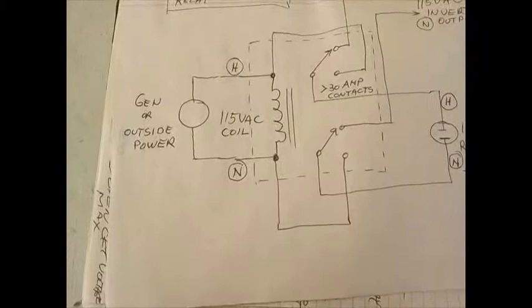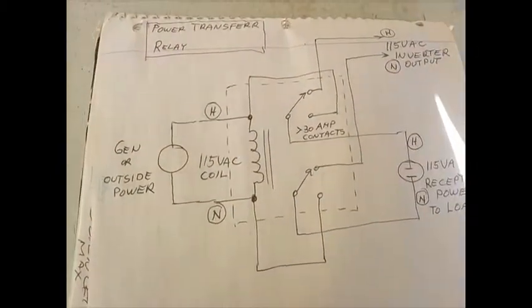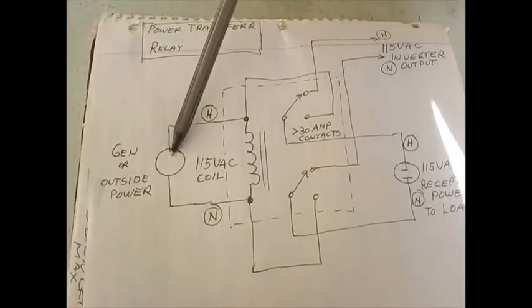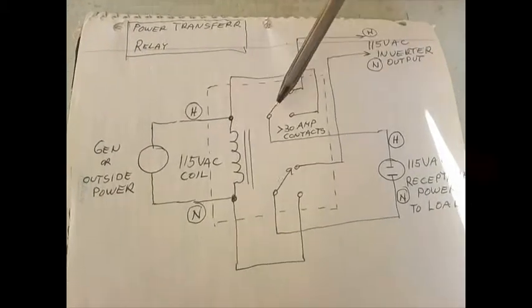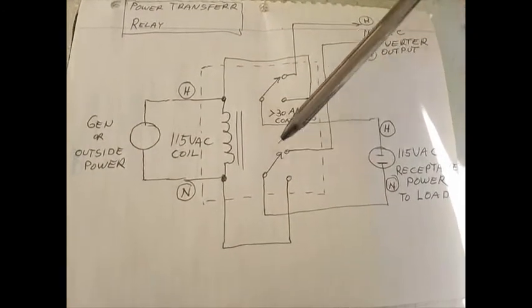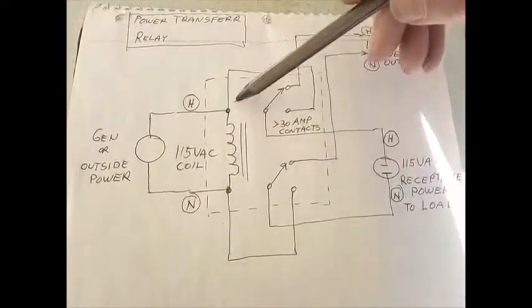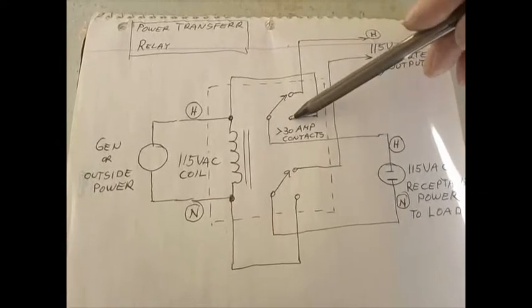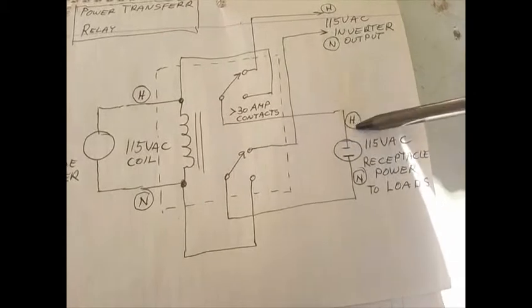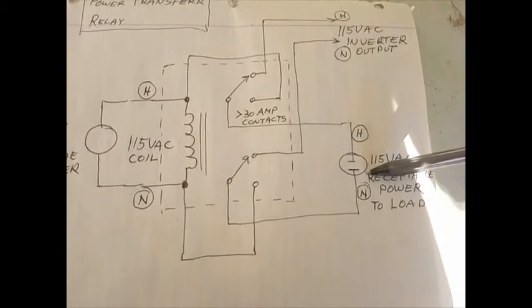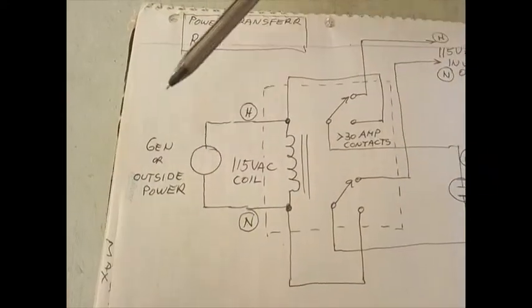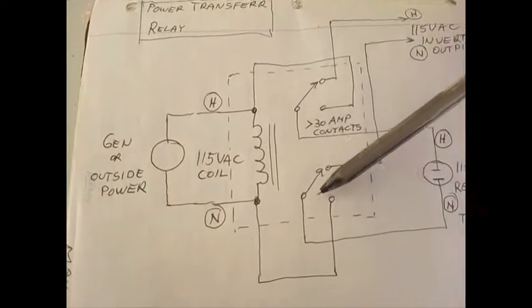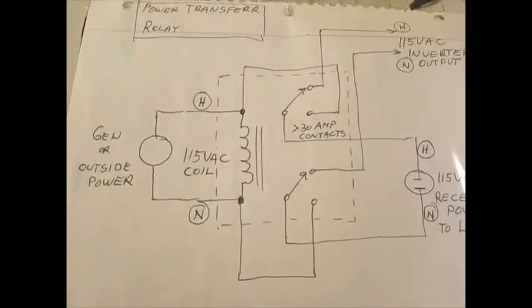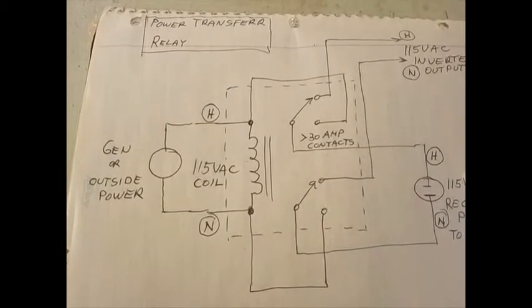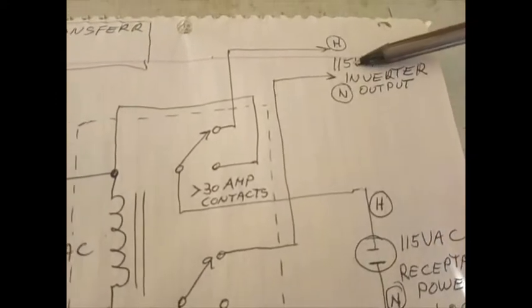I just want to show you a drawing of what's inside that box. Here we have the outside power or the generator, and when that is powered up, it'll energize the coil and make these switches go into the lower position. And then you have the straight through outside power coming to those contacts when the armature is pulled down. So now you're seeing outside power at the output. This is distributed to all the loads in the trailer. Once the generator switches off, the relay coil is de-energized and it will go back to the shelf position of the armature, which means that the inverter output is now the active agent powering the trailer.